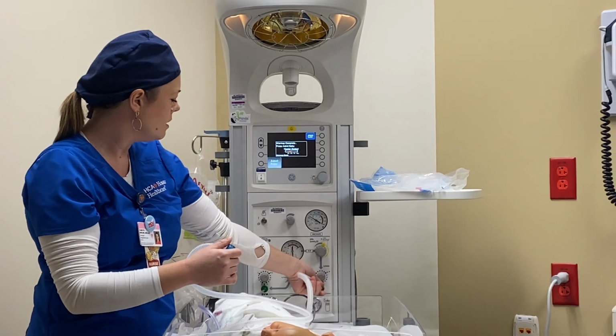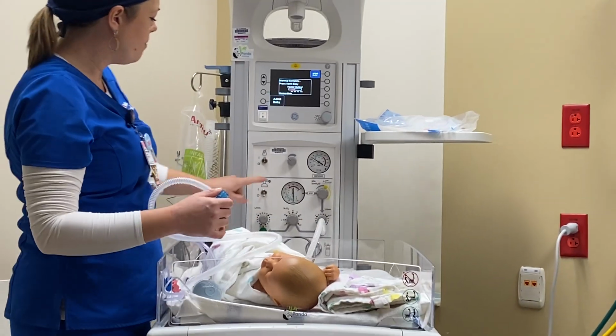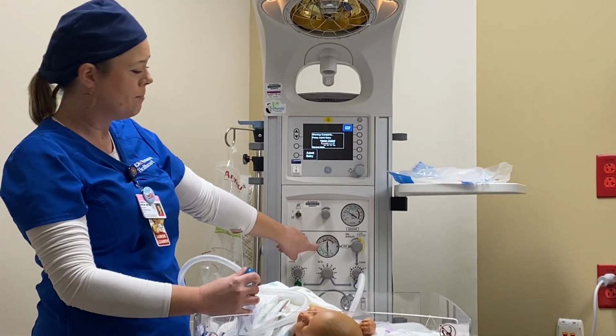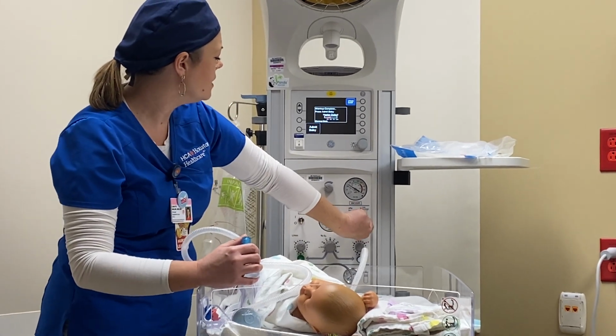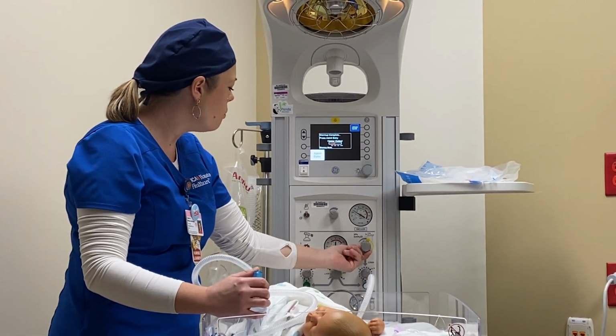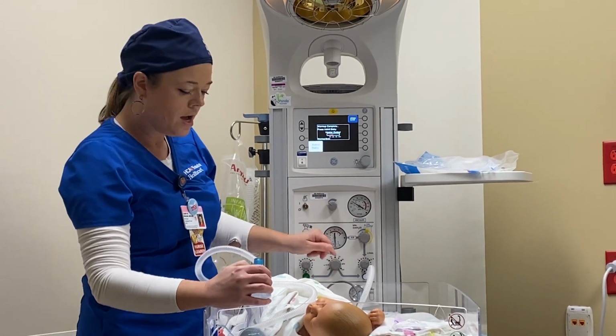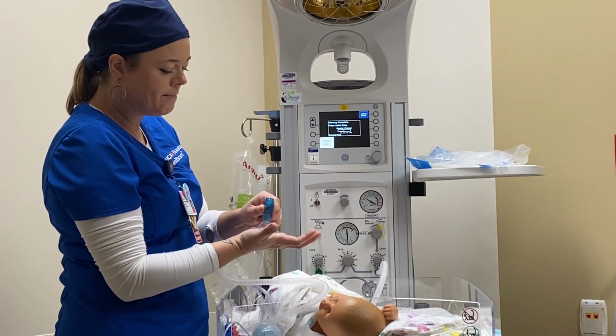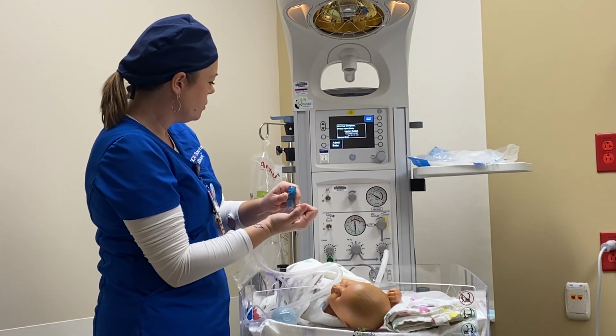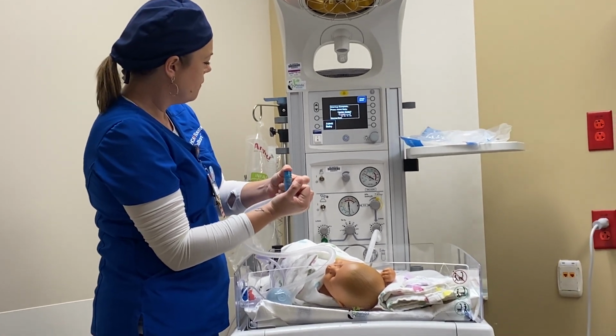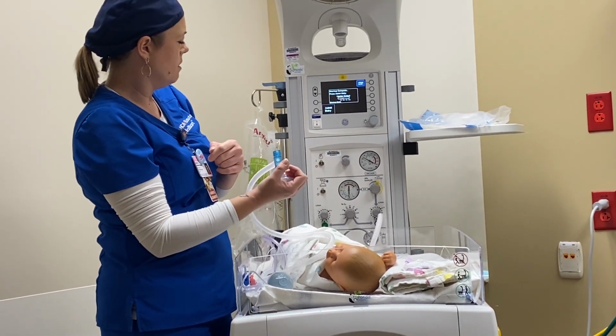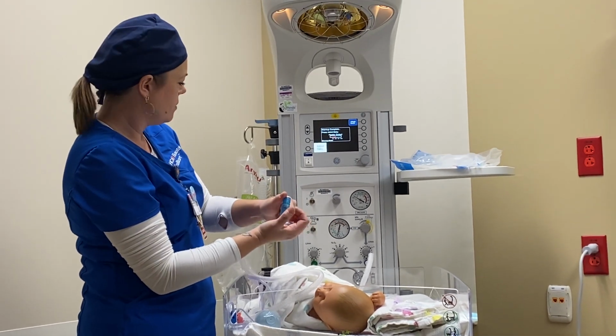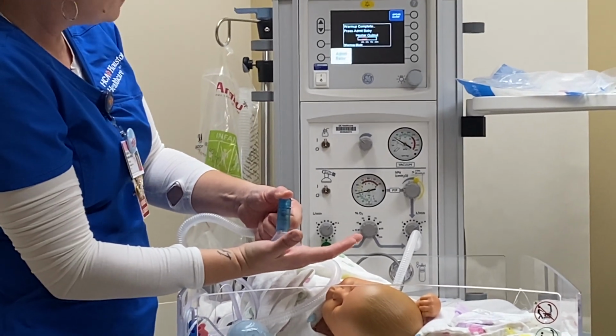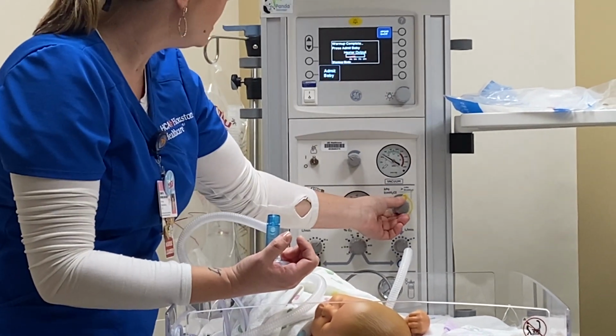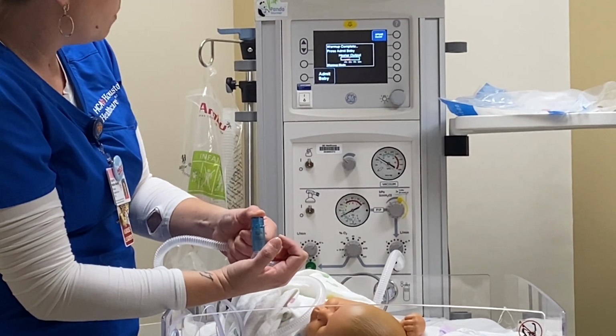So once you plug it in, you're going to adjust your PIP first, peak inspiratory pressure, okay? So this dial here adjusts your PIP, and you want to keep that at a level of 20. You test it and make sure you're at 20 by occluding the mask on your hand, and then you put your finger over the top. Flip it on first. You put your mask on your hand and put your finger over the top. When my finger is on the top, I should get to 20. This is a little high, so I'm going to dial down, and now I'm at 20, okay?